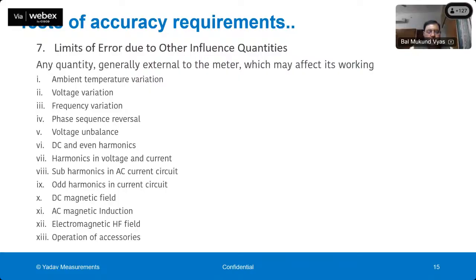So if I take the example of our house, normally we should get 240 volt plus minus 6% as per the Electricity Act, Electricity Rules. But we find that sometimes voltage is 260 volt, sometimes even 180 volt. If you go to villages, sometimes very low voltage is there. So the accuracy of the meter has to be maintained in all these voltage variation conditions, and the standard specifies how much the error can vary with these voltages. As I told you, this is there in OIML and Indian standards.